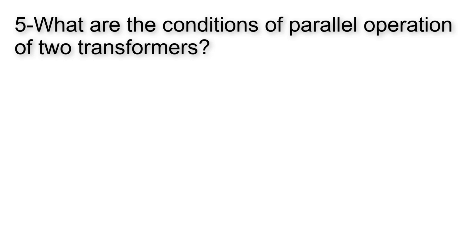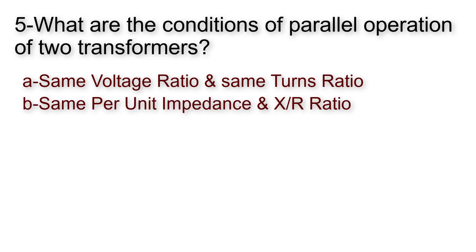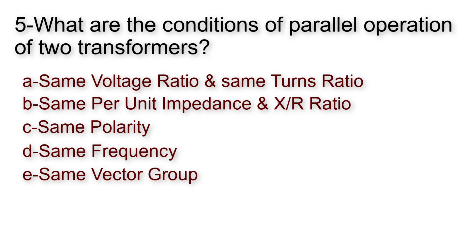The first condition here is transformers must have the same voltage ratio and turns ratio, then same per unit impedance and X over R ratio, same polarity, same frequency, same vector group, same phase sequence, and at last identical position of tap changer.